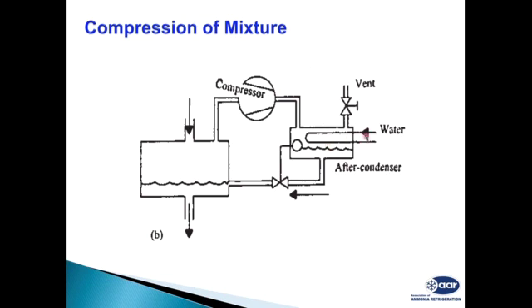It can be air cooled or water cooled. It has a separate compressor, so you need to maintain that compressor, and a different refrigerant is used in it, so you need to maintain extra spares. You need to maintain those parts, and in case of failure of the compressor, this whole unit will fail. The advantage of this unit is that it can remove the air even if the plant is not running. If your plant is not running, it will still keep on removing the air.